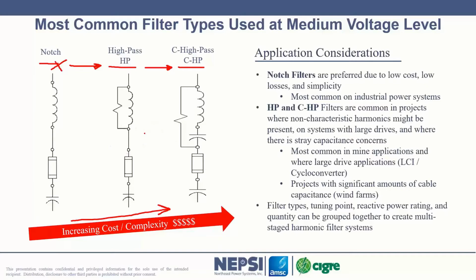These two filters are very similar in their impedance characteristics. The key difference there is that this one is missing its fundamental losses. The loss is at 50 hertz or 60 hertz. And that's because this X of L here is tuned to X of C here. And they're equal to each other at the fundamental, meaning no volts here, meaning no volts across the resistor, meaning no losses in the resistor. It allows us to decrease the value of the resistor here to a much lower value, a lower dampening point, which means it's a higher damped filter system.